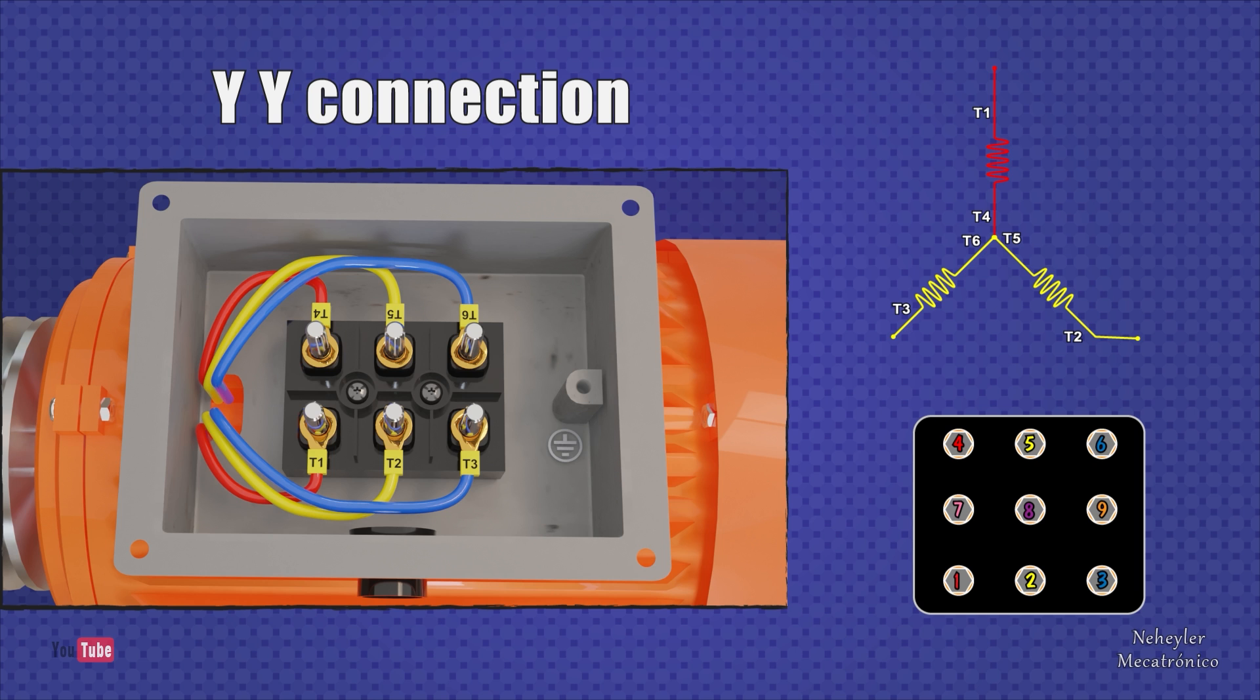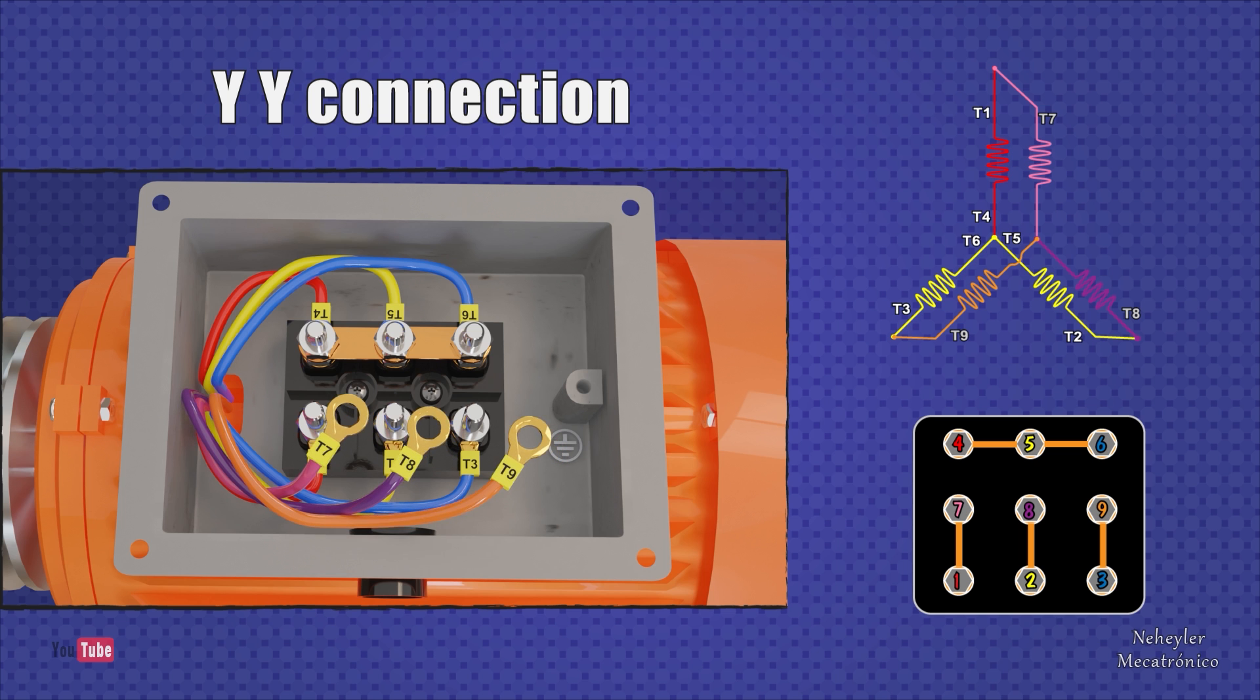What we need to achieve here is to make a star connection. To do this, you must join Terminals 4, 5, and 6 using metal plates. Since we already have the star connection, then we join the three remaining terminals that already have their internal star connection.